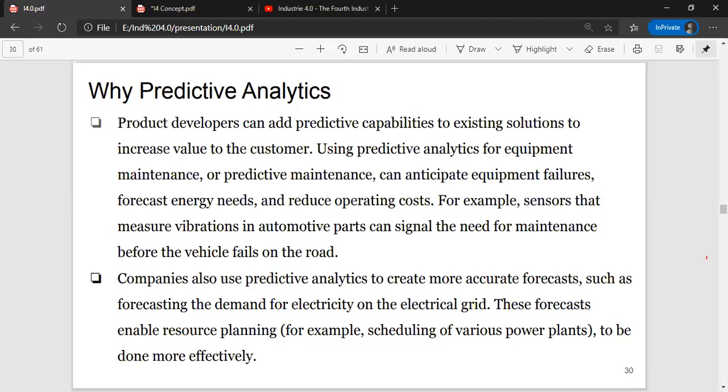So we had an R&D setup in Bangalore, and one of the problems the corporate gave us was this: we have these machines. Given some set of captured data, can you write a model which will predict failures? Let's say there's a magnetic coil in one of these scanners, probably one of the most critical items. Can you predict the failure of the scanner 2 weeks in advance with maybe 60 or 70% accuracy, so that we can ship that part across and replace it?